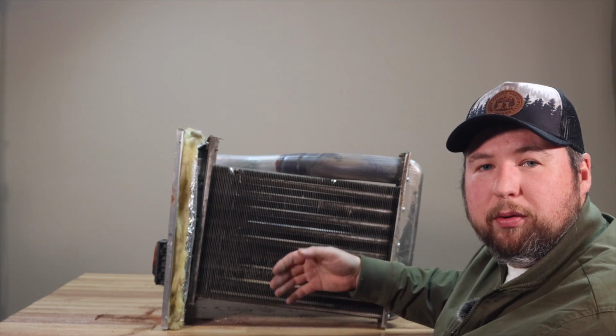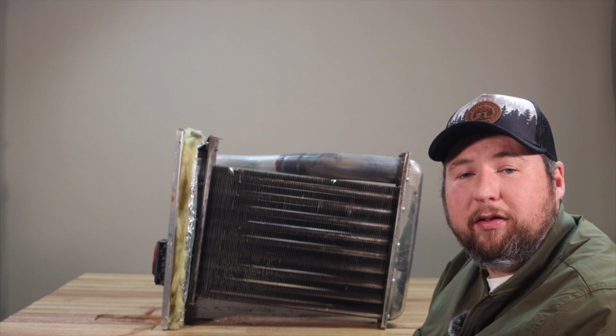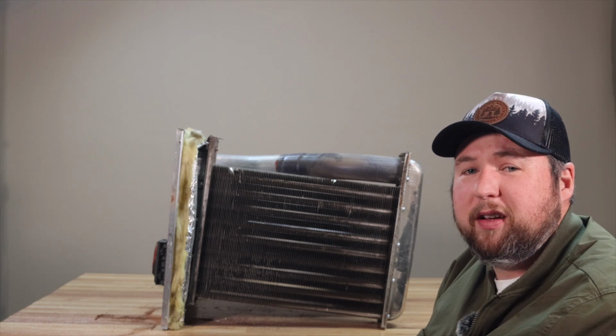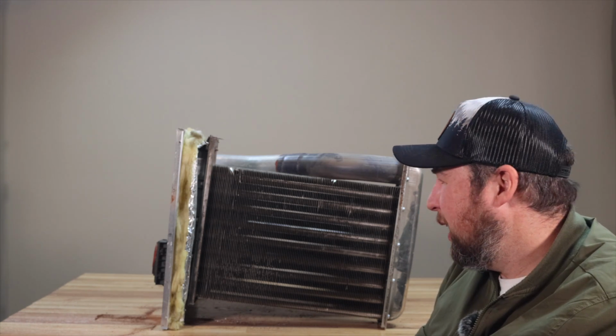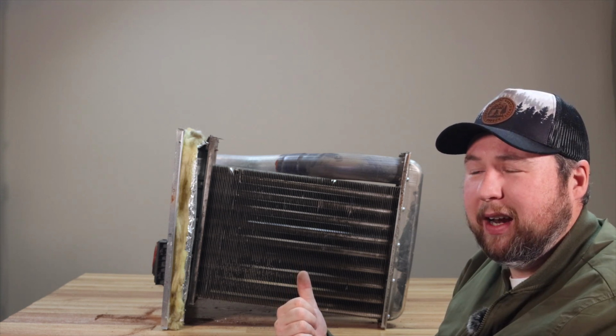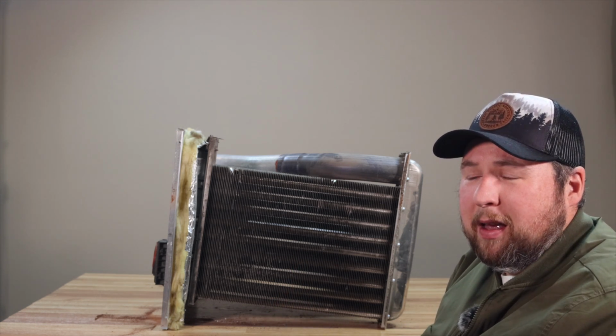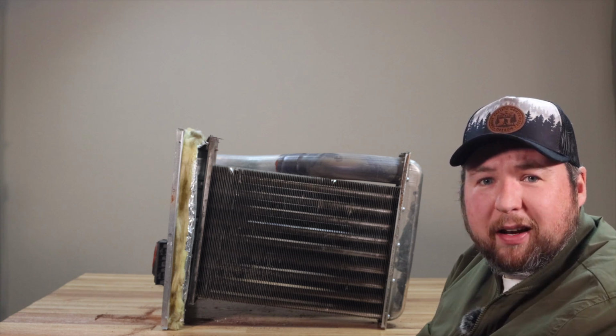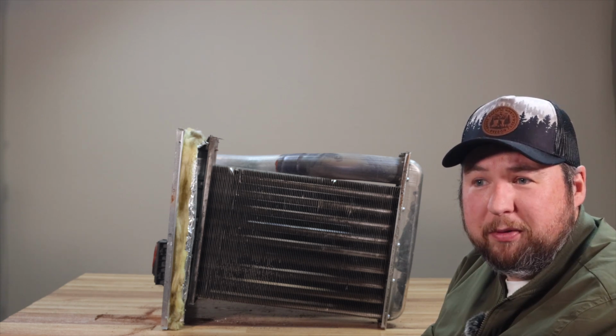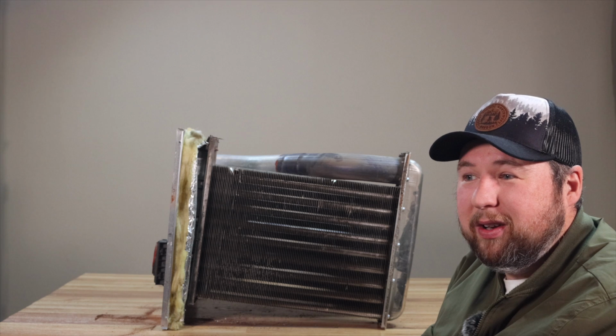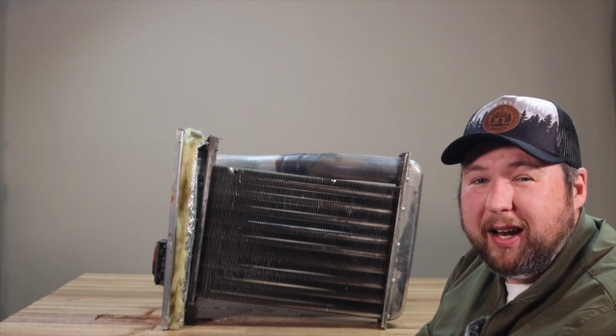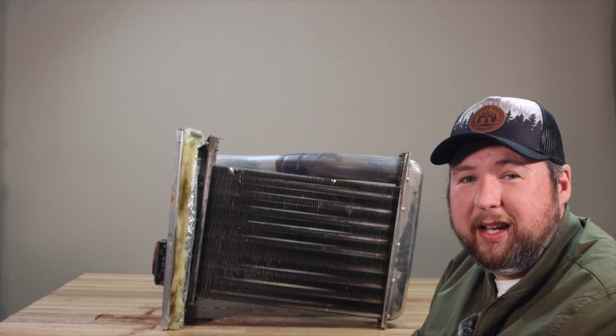Right? Now, because you're doing that, the temperature of your exhaust has dropped drastically because you've pretty much sucked up all the heat. These things can go up to 98%. So they're 90 to 98%. So that means you've got 90% of your heat going into the home, 10% out the exhaust, or you can have up to 98% in the home with only 2% heat loss.